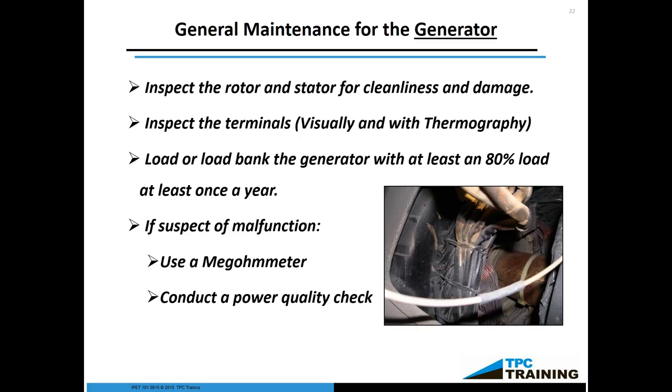Every now and then use thermography — a lot can be told by a thermographic test of terminals. Load or load-bank the generator to at least 80%, at least once a year. The purpose is to make sure the components of the generator — like the exciter — work effectively, and that the generator can handle the load without overheating. If you suspect a malfunction, you can megger a generator just like you do a motor — that will tell you if you have any current leakage across any of the insulation inside. You can also have a power quality check conducted, which will tell you if you have a compromised rotor that the megger didn't pick up. These are typical maintenances that should be done on a generator. And as mentioned, the maintenance on the generator itself is relatively easy compared to the diesel engine.